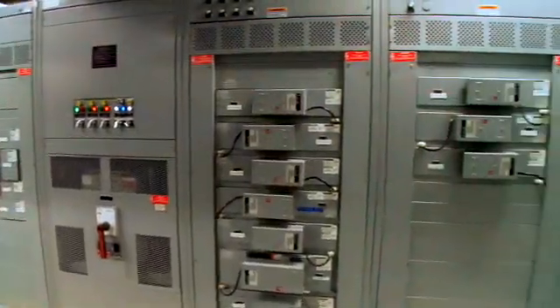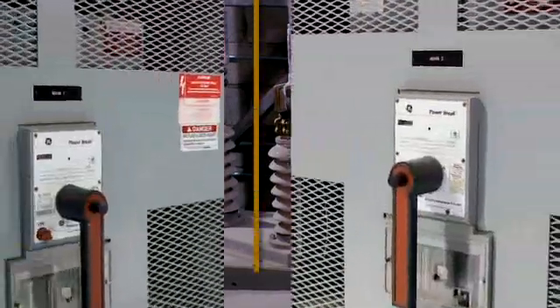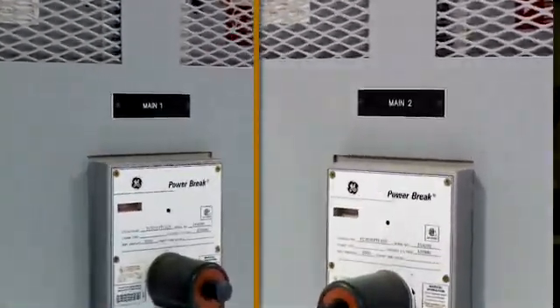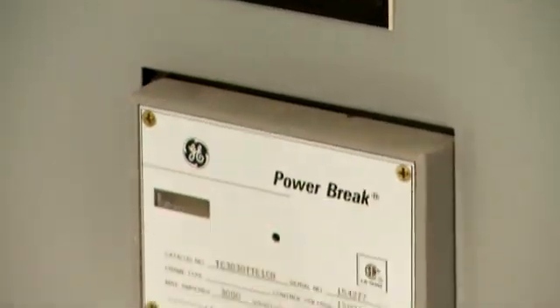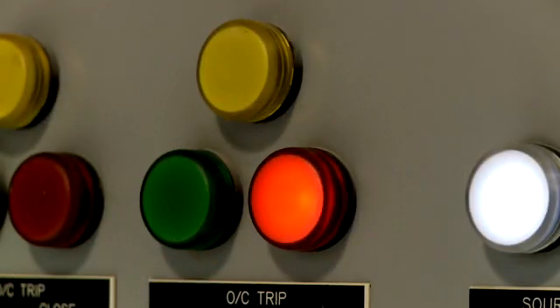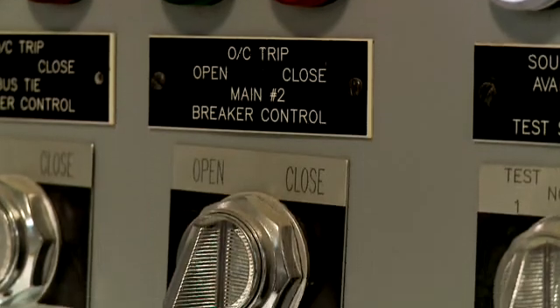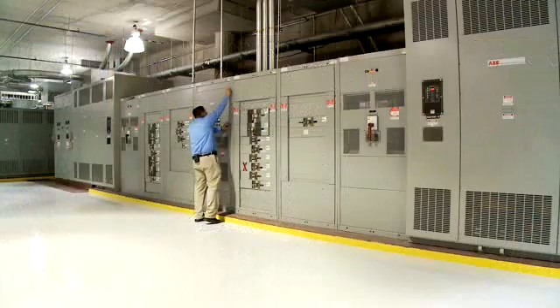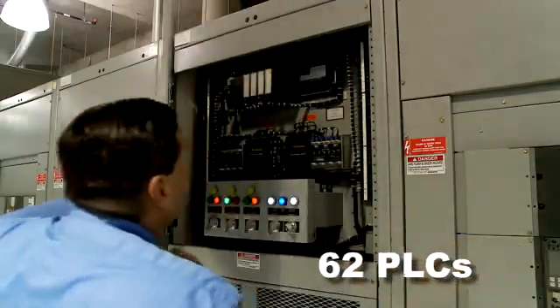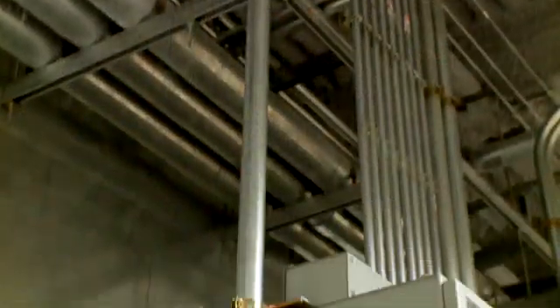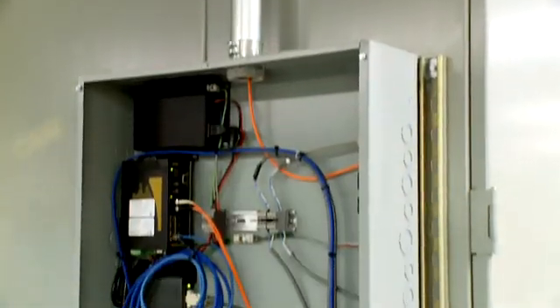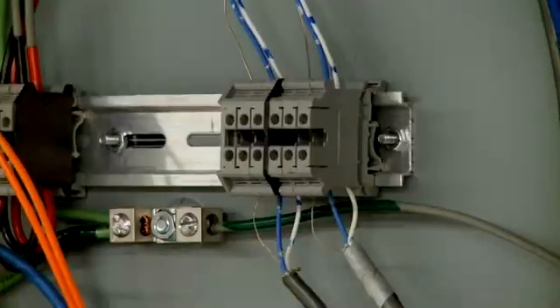A typical double-ended substation has isolating switches, a main transformer, and a main breaker on each end, with a tie breaker in the middle. As long as both utility power feeds are available, both main breakers are closed and the tie is open. 62 PLCs are used throughout the property, and all the monitoring and control communications occur over a secure and dedicated fiber optic based Ethernet network.